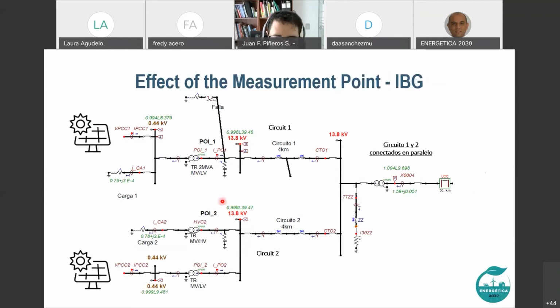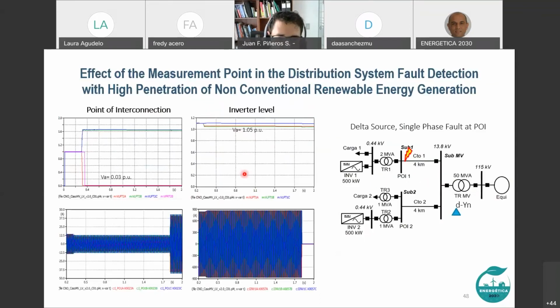This was the network we were simulating, changing the connection group of this transformer, delta or Y, and applying failures in some parts of the network and checking what would happen. For example, this is the case where the transformer is in delta. If you have a single phase fault at the point of interconnection, you can see it at the level of the medium voltage, in this case 13.8 kilovolts.